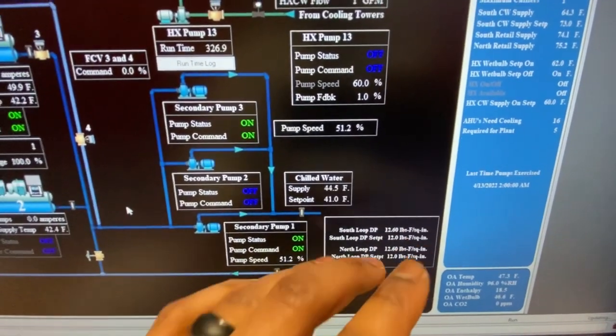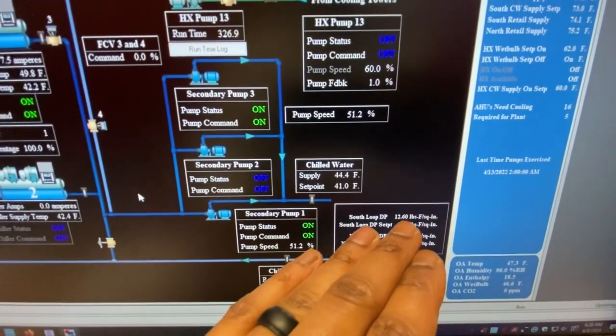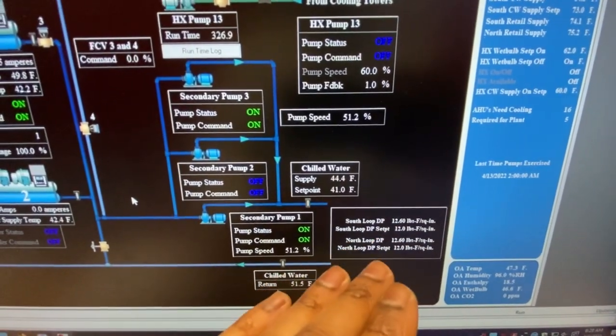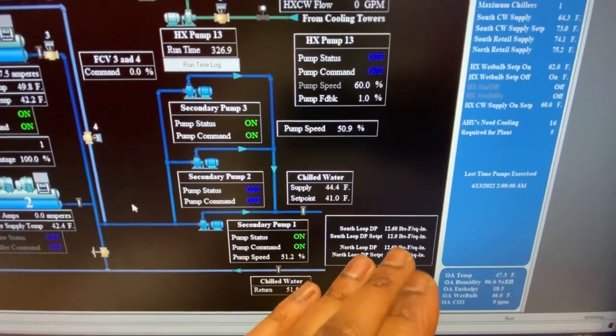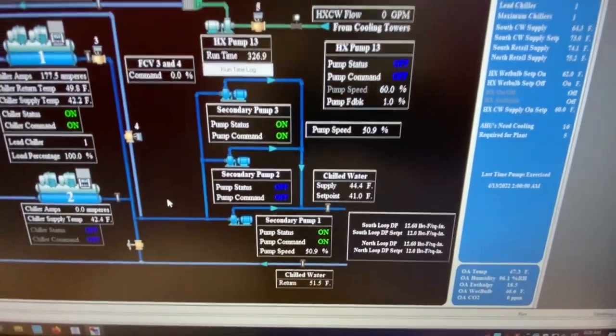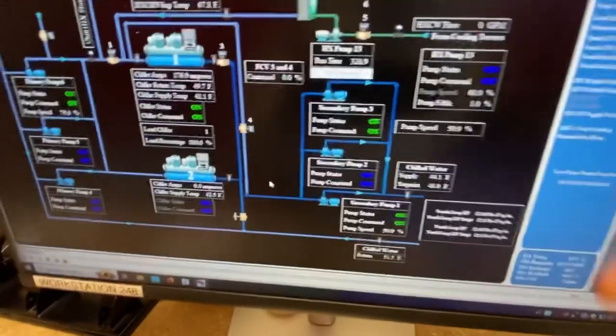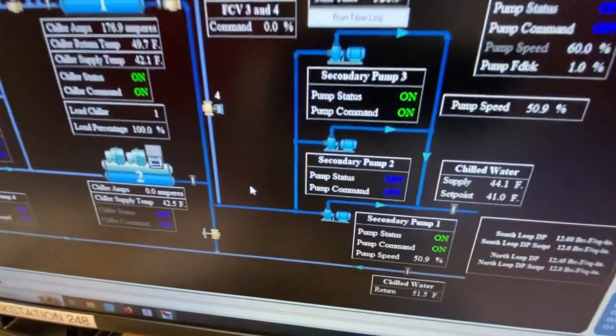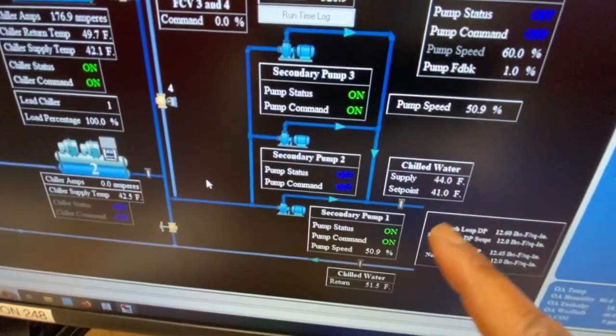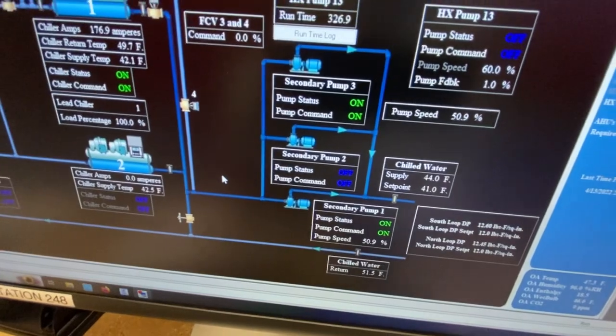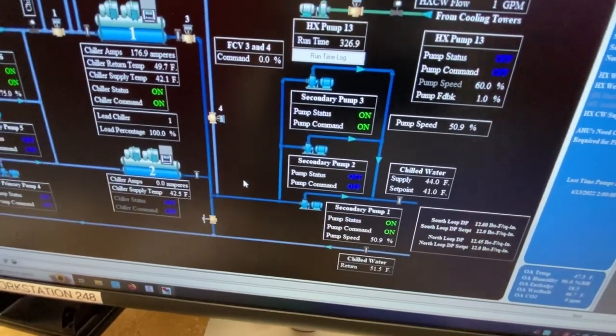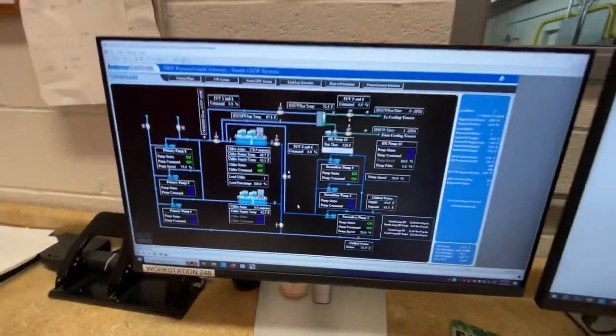If I can keep the DP high at the number it is, even if it gets to 10, that's fine. I just don't want to see numbers from like 8 going down, because at that point I'm not cooling the building anymore. So that's what I do right now. I'm gonna leave the set point at 41. I don't want to go any lower than that. If I go to 40, I'm not really doing much at that point. So I'll leave it at 41, and hope for the best.